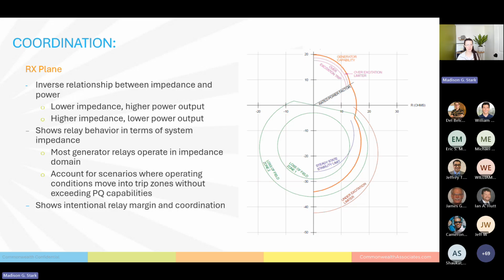So this really shows relay behavior in terms of system impedance, which is important because relays are programmed in the impedance domain. They're programmed to take the voltage and current that they can measure and then calculate impedance. And based on the impedance, they have their designated trip conditions. So this can account for scenarios where the generator might be operating within the defined power constraints, but because of things like changing fault impedance or distance problems that you see between distance type relays, those things have different impedance profiles, even though they have the same power profile.